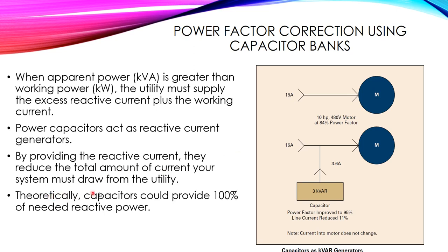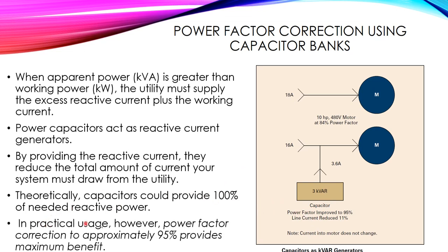Theoretically, capacitors could provide 100 percent of the needed reactive power, so we can use capacitors to achieve a unity power factor. However, in practical usage, power factor correction to approximately 95 percent provides the maximum benefit for our system, and we don't need to increase beyond this value.